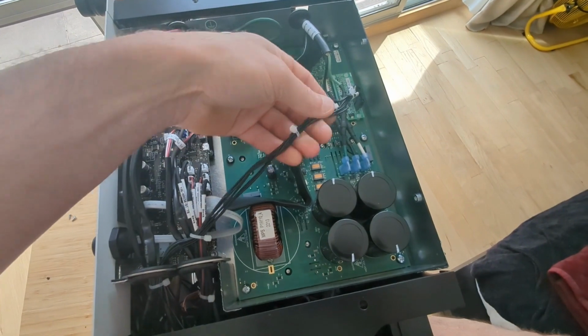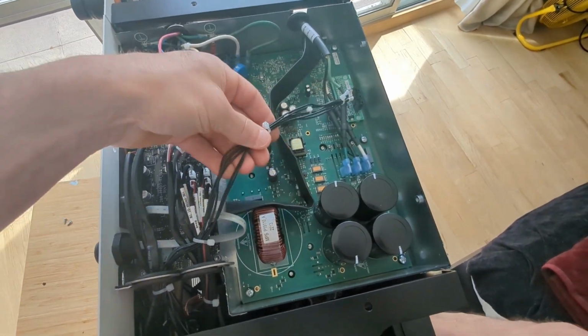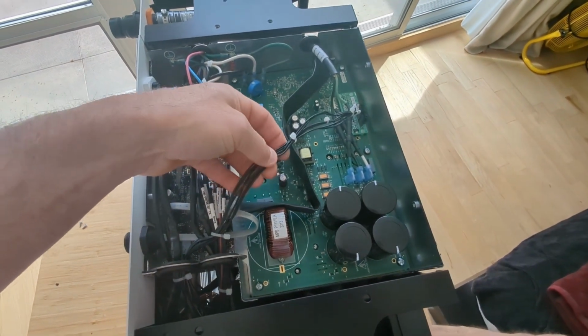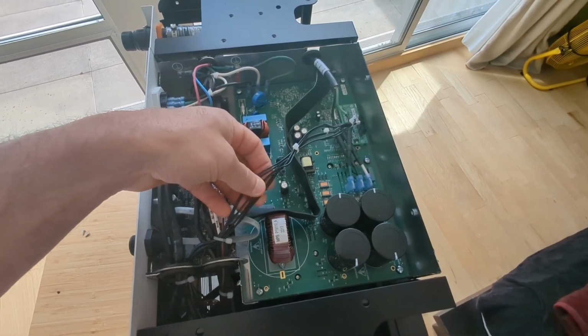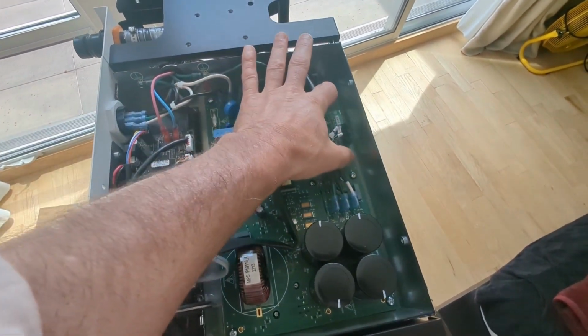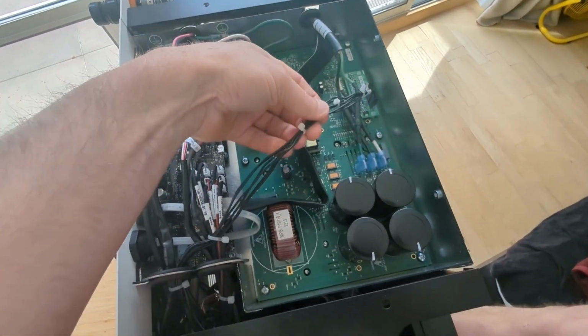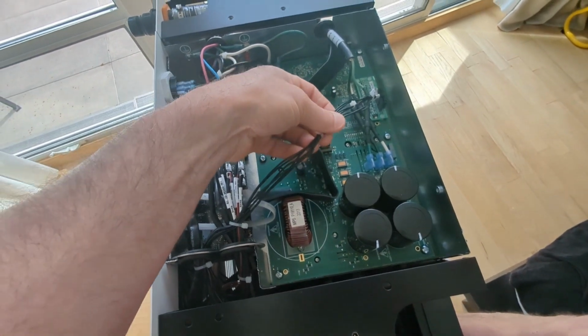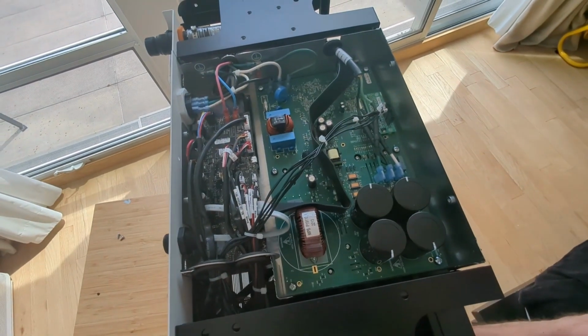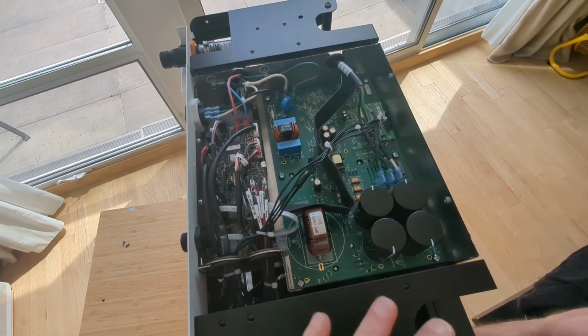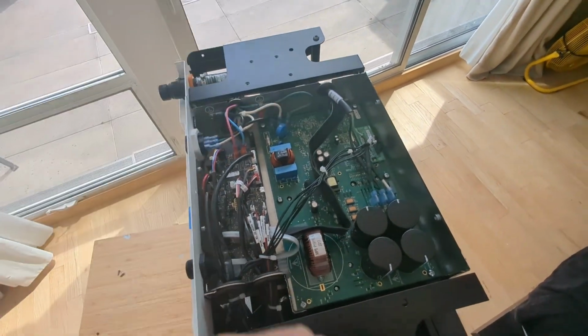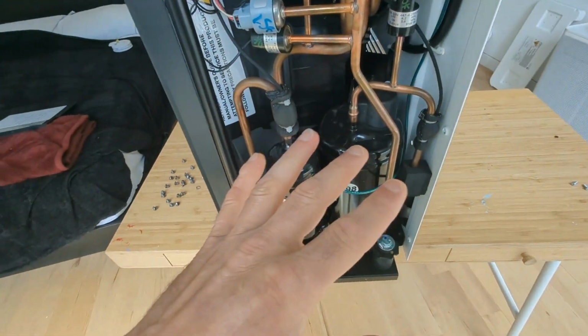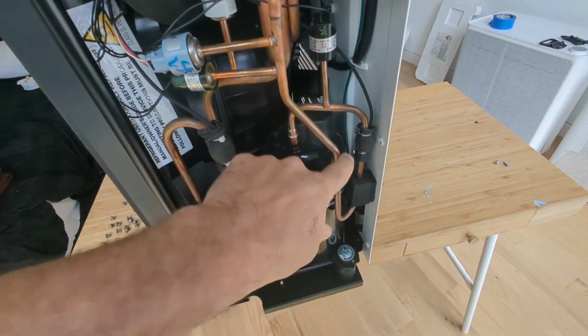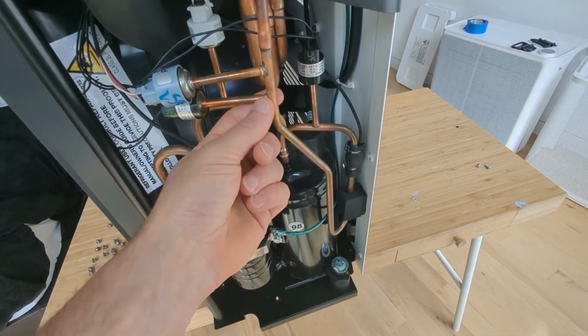Interestingly, these 3 lines here are safety lockouts. Those come from 2 overpressure switches and 1 freeze lockout switch, and they go onto this little daughter board. And if any of these lockout switches trip, it cuts power to the compressor. And the reason you want to do that is because if you have too much pressure running in the high side over here, it could damage the compressor and maybe even blow out one of these connections. And you don't want to do that.